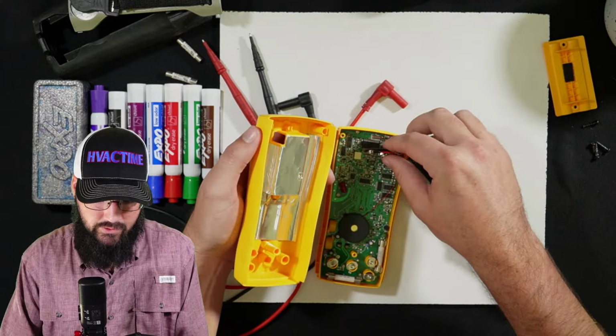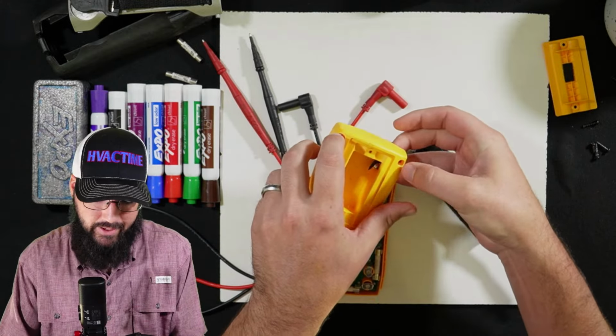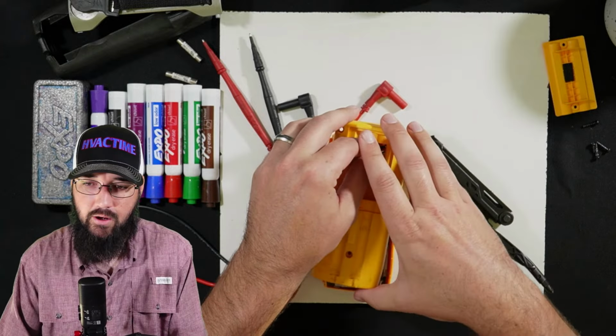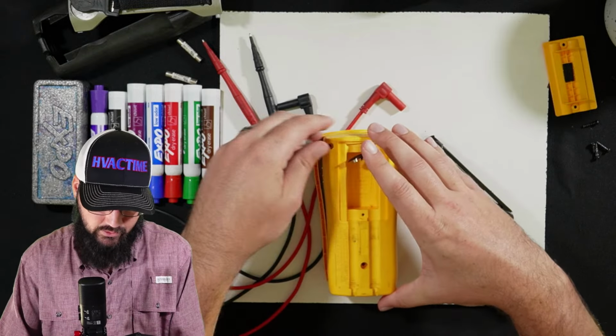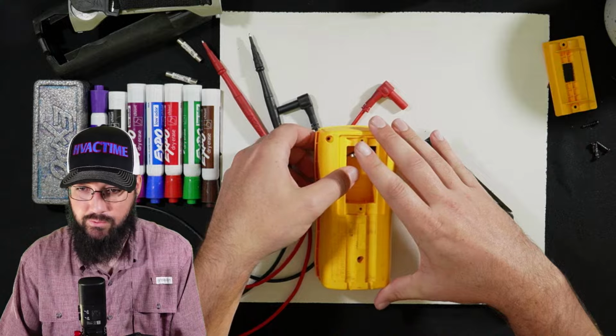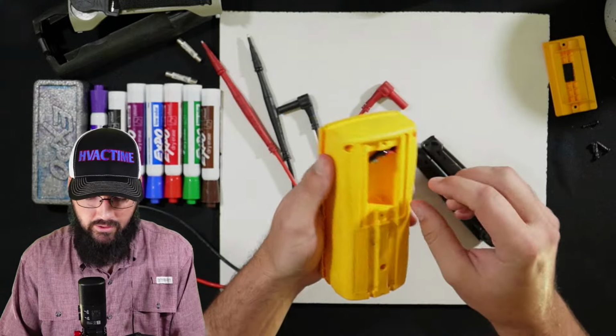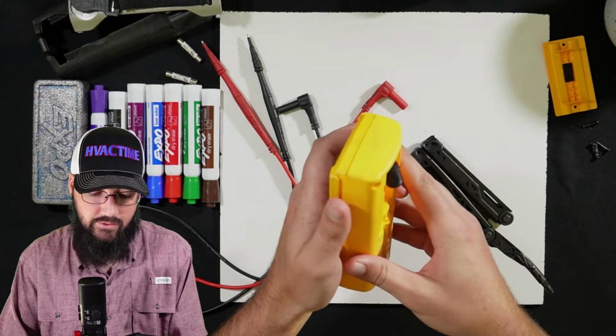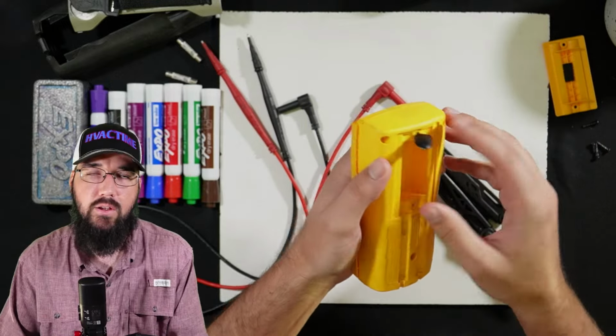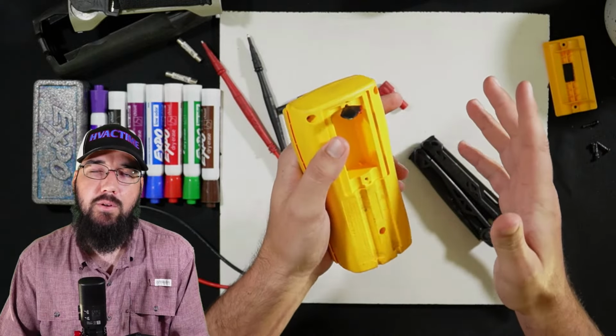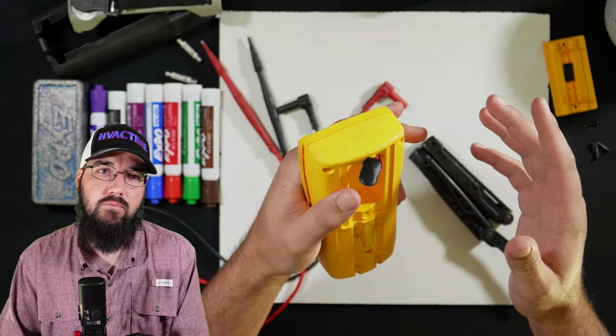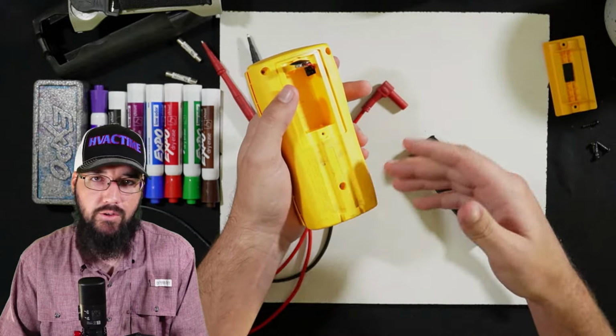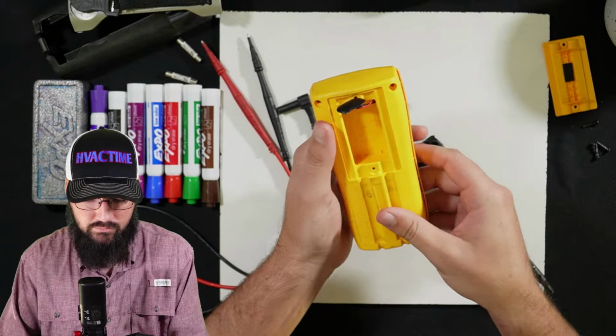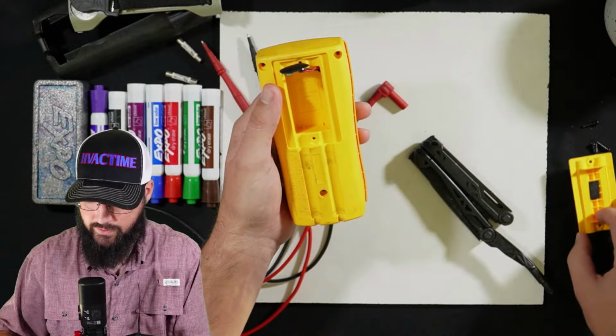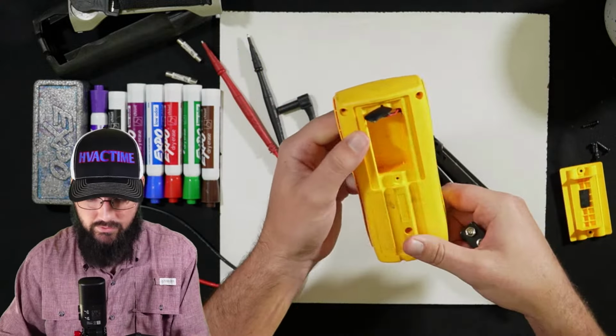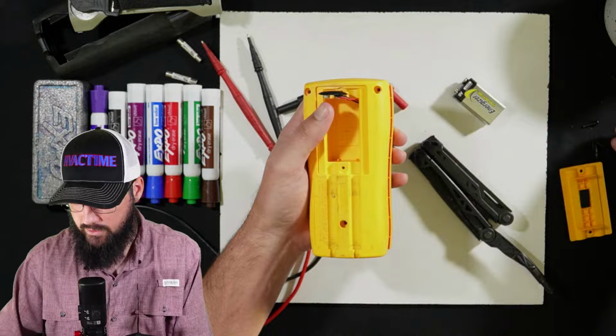All right, so on that Fluke, what's the capacitance range? Like how high can you go? Because most of them I look at max out at like 1,000 microfarads, which for what we're doing on the chiller side is not enough. If you're spending all your time on lighter equipment, RTUs, splits, reach-ins or walk-ins, 1,000 microfarads is fine. That's not going to cause you any issues.